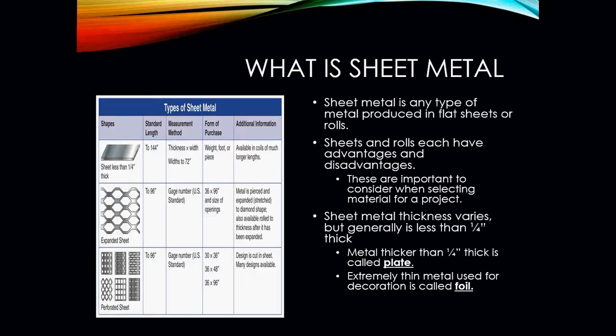So it's really important to know what you're going to do with the metal. In HVAC, it really depends on the thickness of the metal and the construction of the metal. That's important to make sure that when we are introducing air and velocity through the ductwork, it's able to sustain the static pressure and velocity in which the air is traveling, so the ductwork doesn't blow apart and create massive leaks.